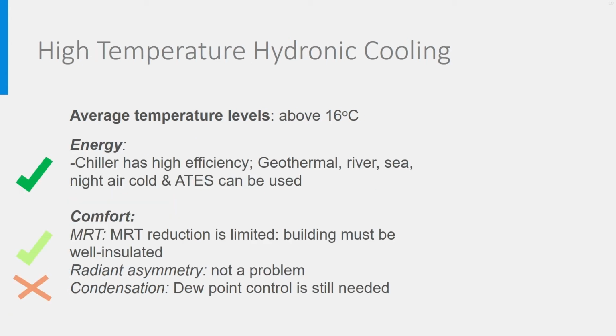High temperature hydronic cooling with temperatures above 16 degrees has the advantage of being produced with a high efficiency, as the chiller needs to overcome only a small temperature difference between heat source and heat sink. Instead of chillers, cooling from natural resources like night air, sea, rivers, or aquifer thermal storage systems can be used, which are very sustainable and produce almost no CO2 emissions.